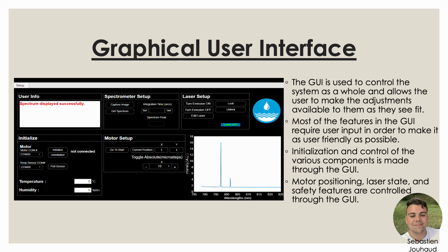In the meantime, the edit laser will run an executable that directly controls the laser. This is due to some proprietary software, and this was the best that the company we got the laser from could provide for us. Finally, we have the lock and unlock. The reason I put this in the laser section is that it's mostly a feature to prevent people from looking over the top of the laser when it's on. There's a latch at the top of our system, and if you hit lock, it will not be able to open up. When you hit unlock, it is able to open up. Normally whenever you're running the laser, you would hit lock so you wouldn't be able to open the little latch and get the laser shining directly in your eyes.